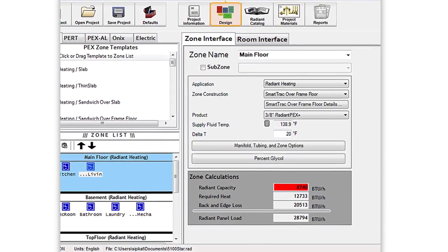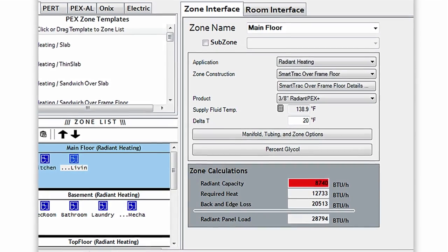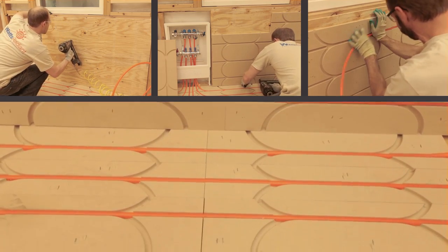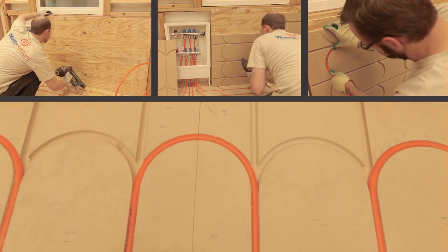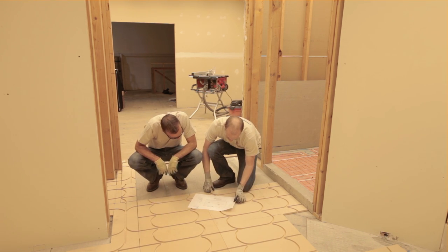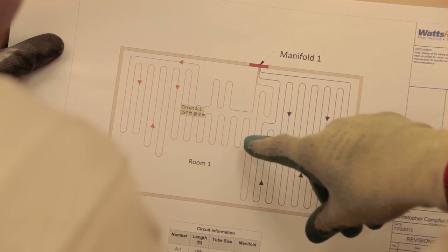To prevent underheating, calculations should factor in the temperature limits and R values of construction and flooring materials. If necessary, supplementary heat can be added by installing SmartTrac panels on the walls or ceilings. To simplify installation, create a drawing that details the tubing and panel layout. Ask your local Watts Radiant representative for assistance if you are not set up to create your own.